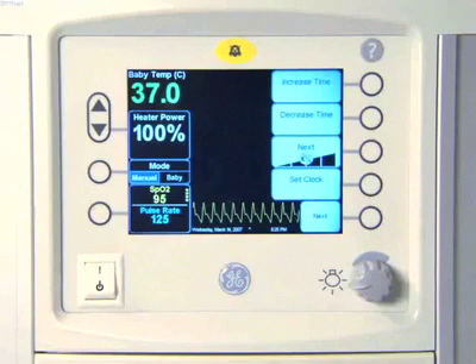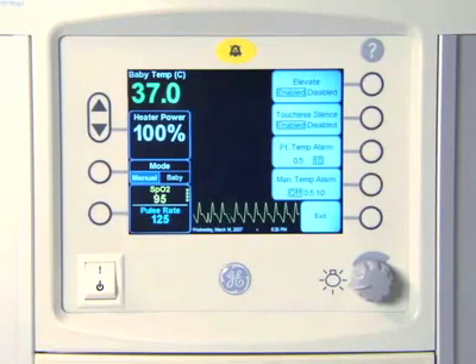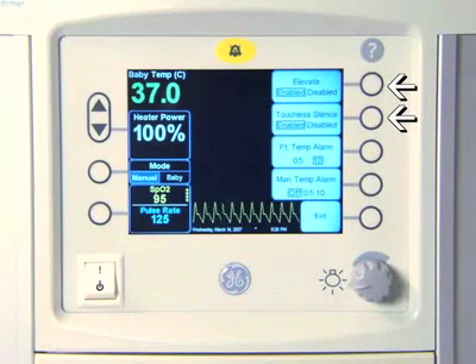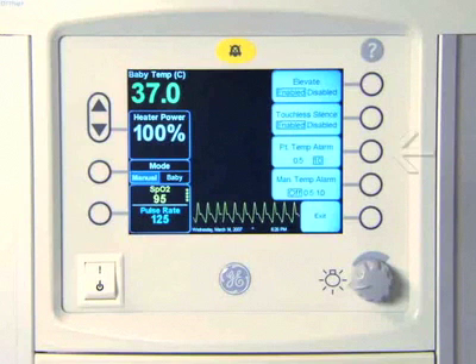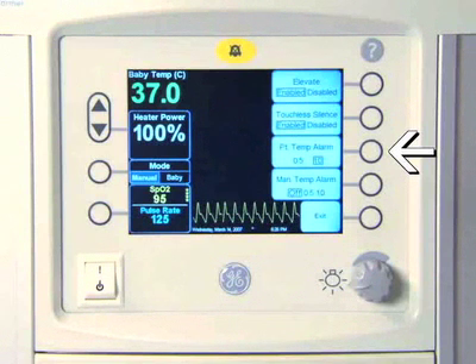Touching the Next key brings up a new group of options. The Elevate and Hands-Free Alarm Silence keys allow you to enable or disable those features. Push the Patient Temp Alarm key to choose between two settings in the PandaWarmer's baby mode, 0.5 or 1 degree Celsius. When your baby's skin temperature exceeds the set temperature by greater than plus or minus 0.5 degrees Celsius or plus or minus 1 degree Celsius, you will receive a baby hot or baby cold alarm.